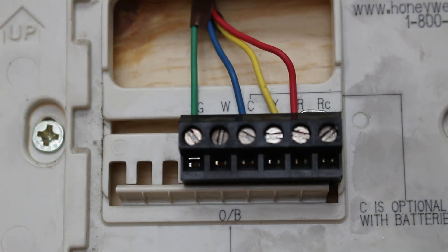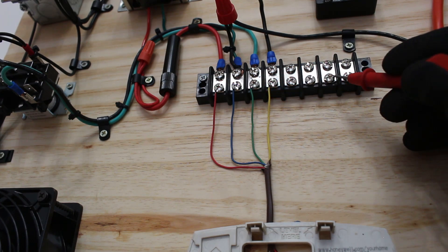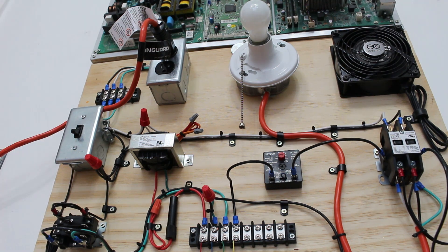Let's go ahead and trace these wires to our low voltage terminal block. We follow our wires. Here is our low voltage terminal block: R, C, G, and Y. Power has now been applied to our unit and we can begin troubleshooting.